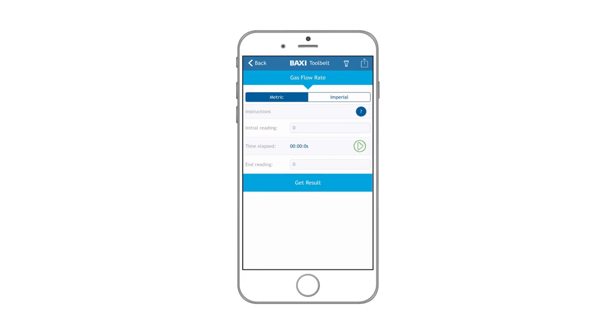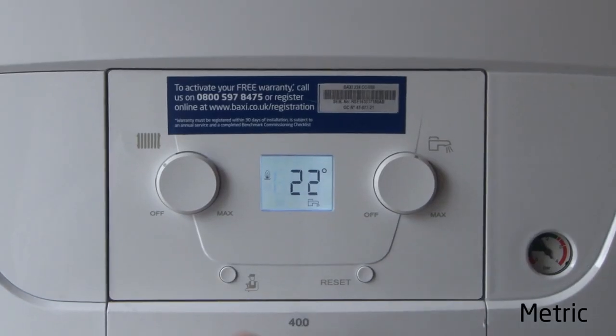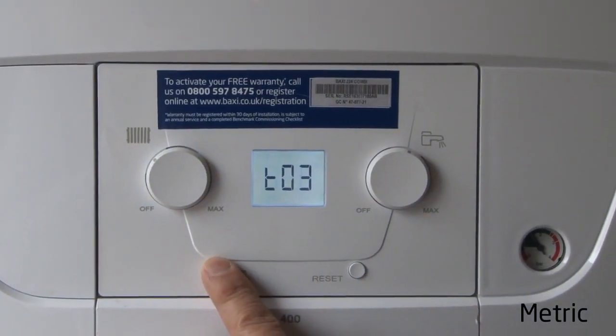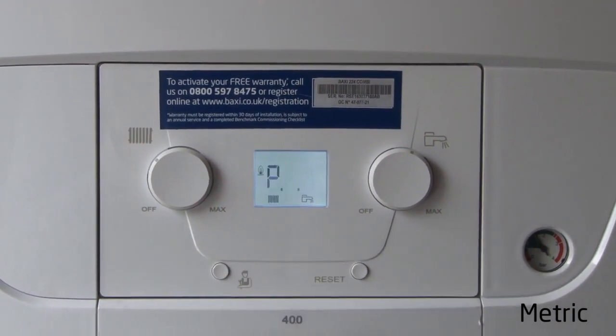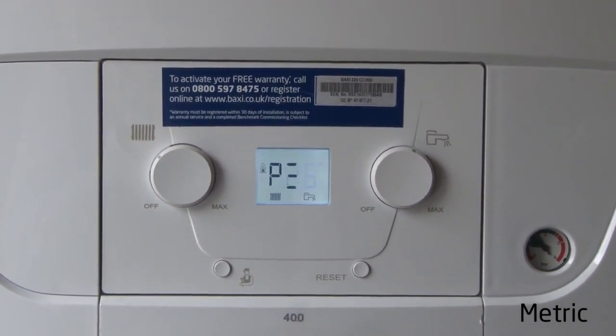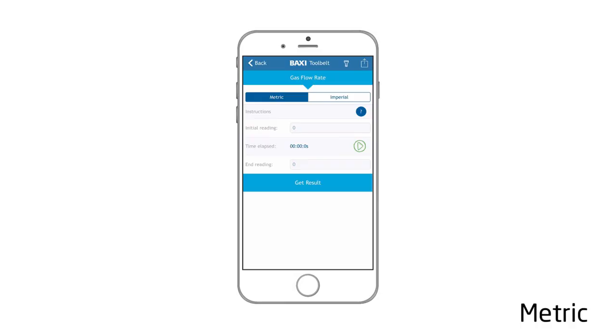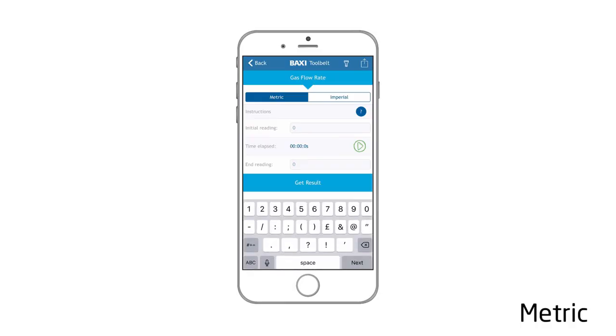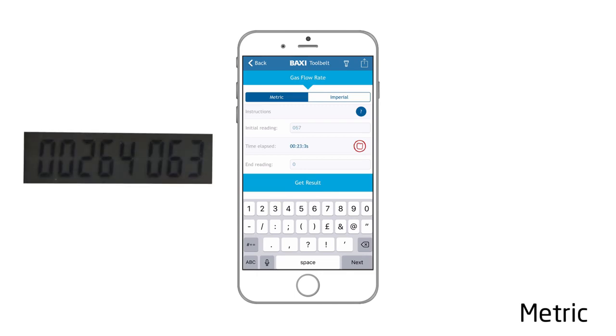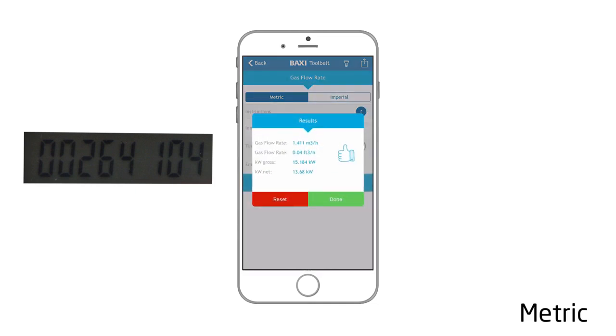If your meter is metric, do the following. Set the boiler to maximum workload, take the reading off the gas meter, input the last three numbers into the initial reading section and start the timer. Wait until two minutes have passed and then stop the timer. Then again input the last three numbers from the gas meter into the end reading section and click get result.